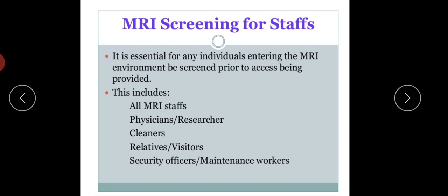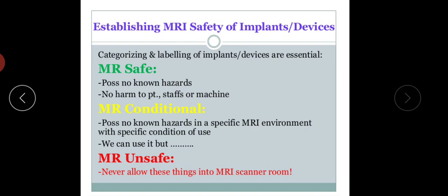Establishing MRI safety of implants and devices. Categorizing and labeling of implants and devices is essential. So, the devices can be categorized into three main headings. The first one is MR safe, which poses no hazard and is not harmful to patient, staff, or machine. Then MR conditional, which poses no known hazard in a specific MRI environment with specific conditions of use. We can use it, but there are some conditions in which we can't. So they are MR conditionals. And the third one is MR unsafe, which must never be allowed into the MRI scanner room.